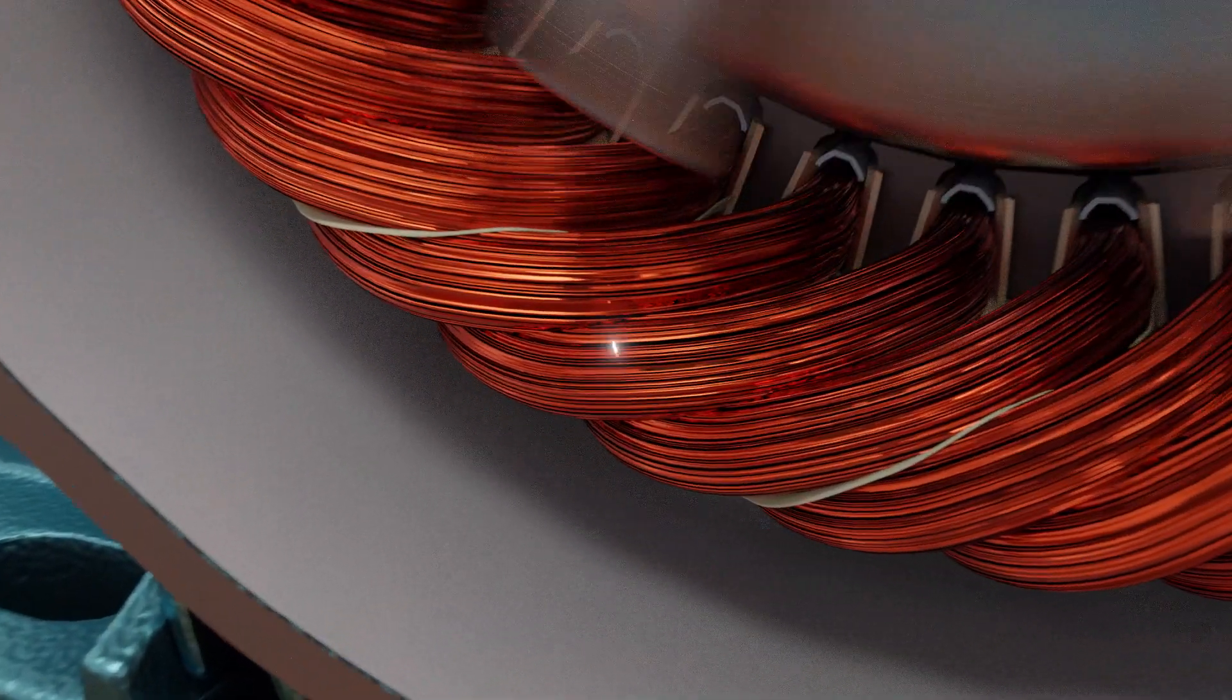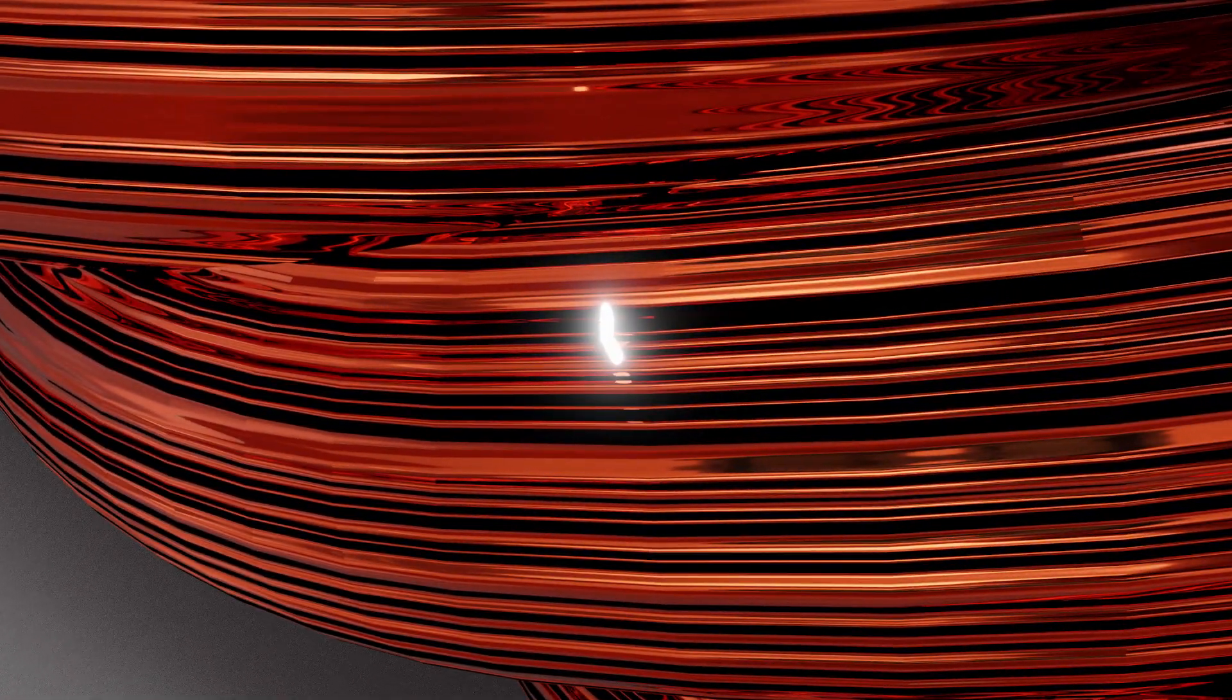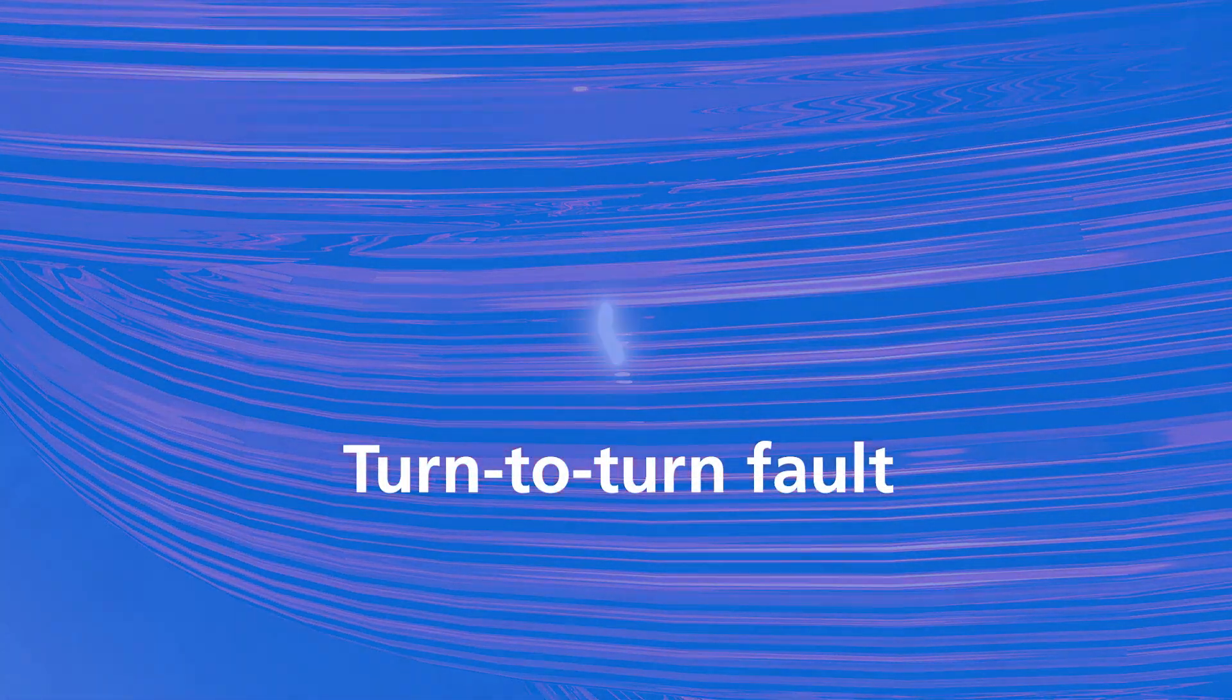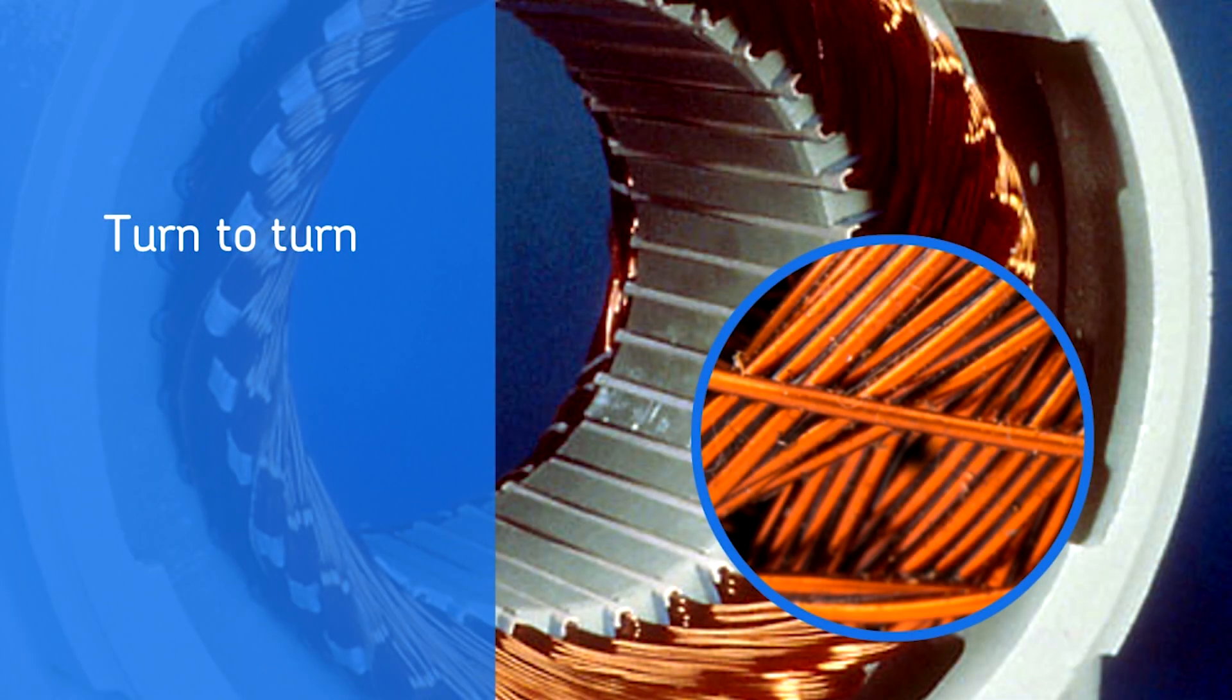The most common insulation failure is between turns of wire that are next to each other in the same coil. This is called a turn-to-turn fault. Other wire-to-wire insulation faults are phase-to-phase and coil-to-coil.